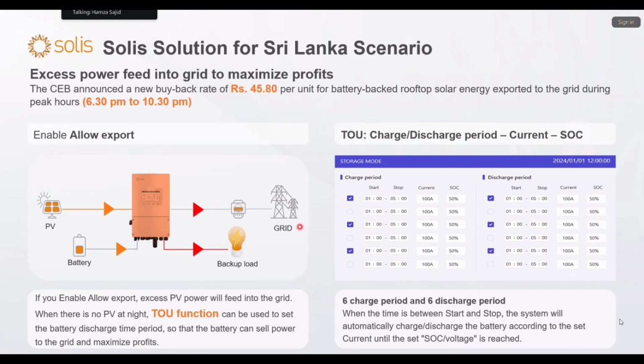So this is the time of use charge discharge period, current and SOC. Current means the battery drainage, how many amperes you want to drain from the battery, and the SOC, how much SOC you want to reach at that time. Like if the battery is already at 40% and you have a charging time period, in this time the inverter will charge the battery at 100 amperes until it reaches 50% SOC. So you can set the times according to this.